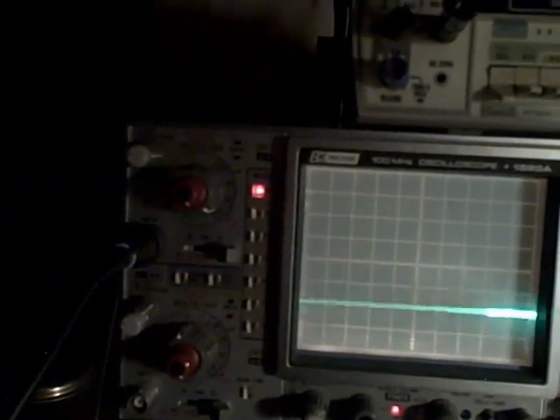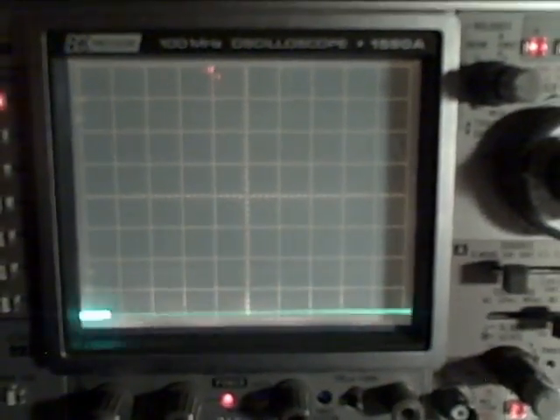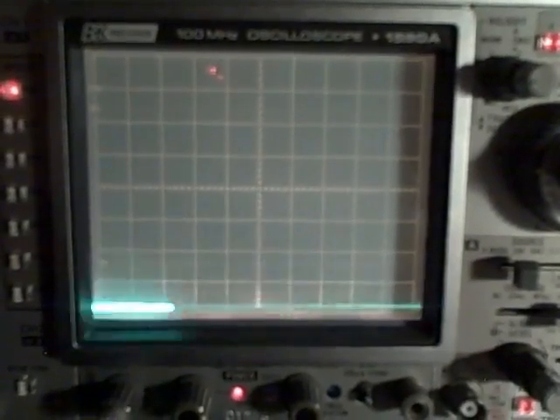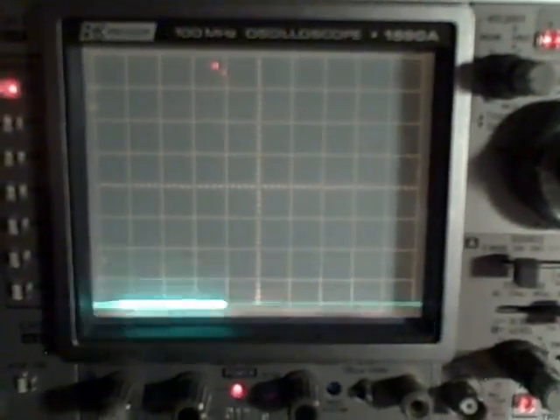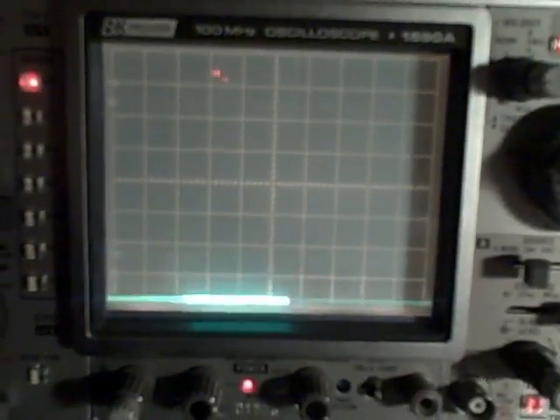Let's go to the 1 millivolt range. And what I've got here is just something above the grounded last step. So that's ground. And that brings me up about half of the smallest mark on my division there, which would be about right. I've got 5 marks in that first division, so I'm supplying 1 millivolt. That would be half of one of those divisions. So here we go. So that's taken us through all of the ranges.